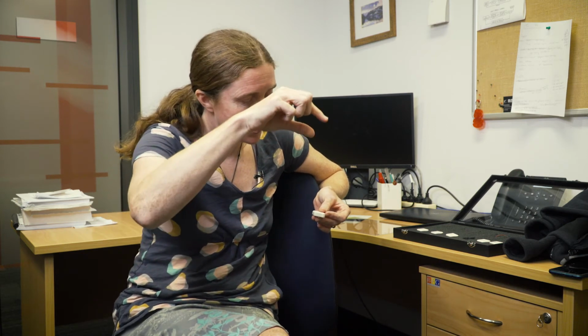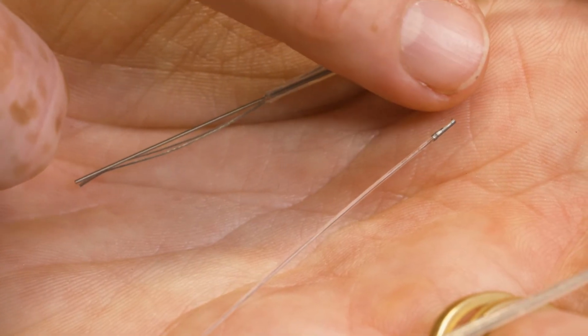Intracranial pressure is an interesting one because the pressure in the brain is very low, usually between 4 and 8 millimeters of mercury, a lot less than arterial pressure. Because that's quite low, the pressure will change with animal posture. If the animal rears up, there's a true change in ICP. With a fluid-filled catheter, because the signals are transduced at the body, you tend to underestimate some of those changes, because if the animal's upright, the fluid-filled catheter is upright relative to the body, and you don't see that response. When the transduction happens at the tip, all of those positional changes, which is actually what the brain is experiencing at those times, will be reflected in the pressure that you're recording.